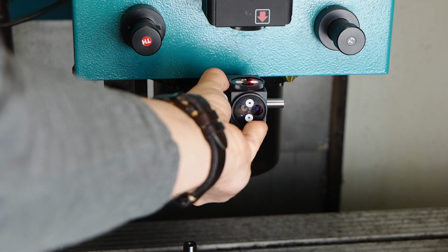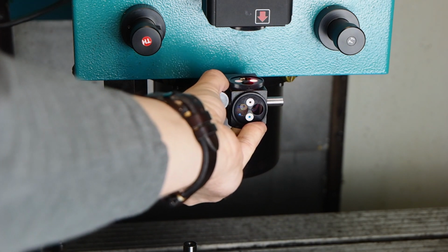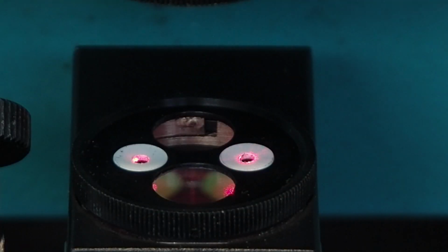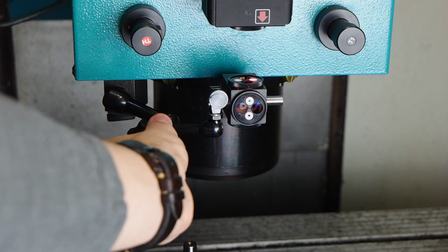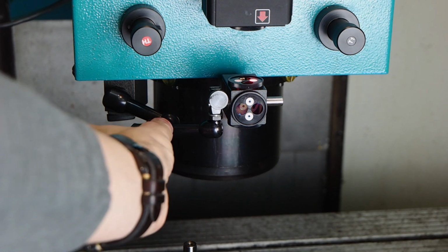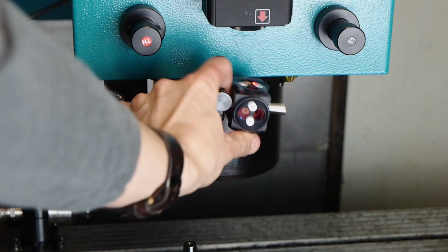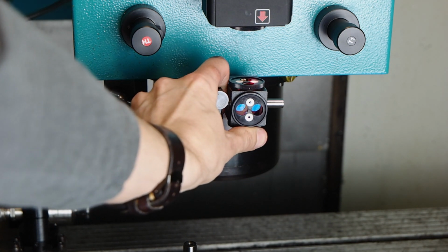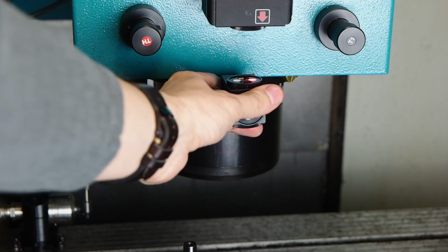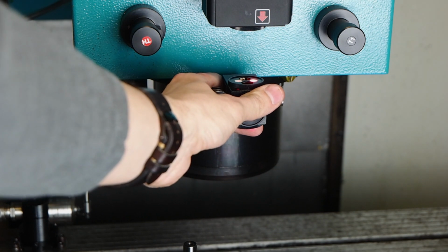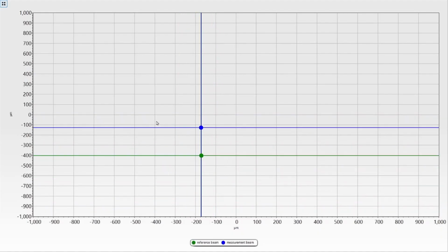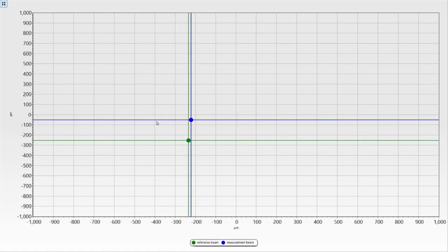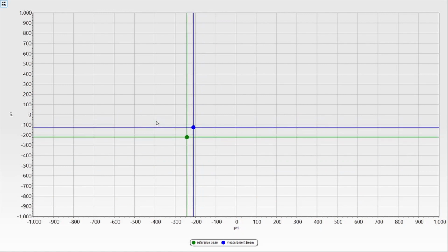Here, you can use the aperture for alignment as well. On the screen, you can see how the correct alignment looks like. Then fix it with the knobs. It shouldn't be too tight though, and adjust it with your hands. The adjustment procedure you can see on the screen. Don't forget to open apertures.